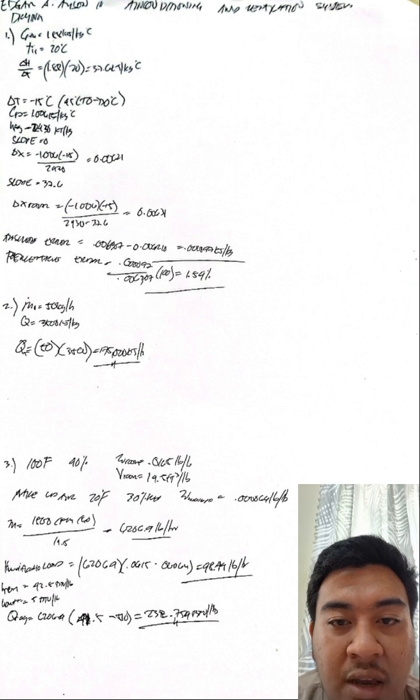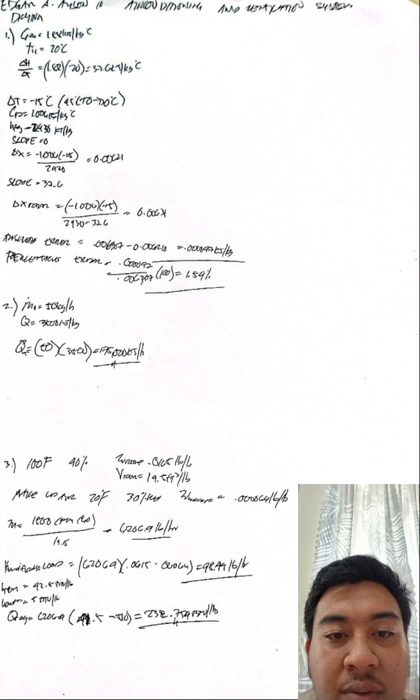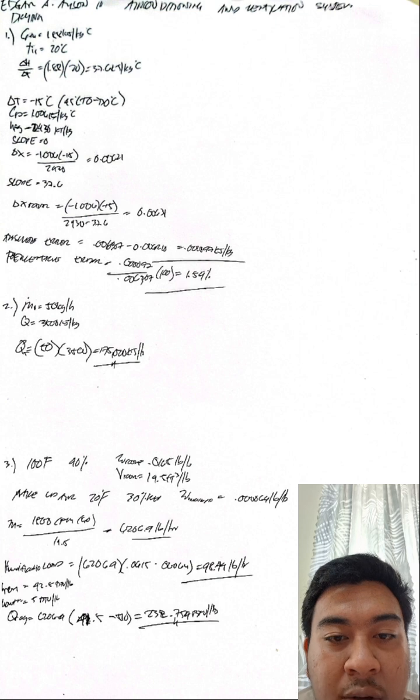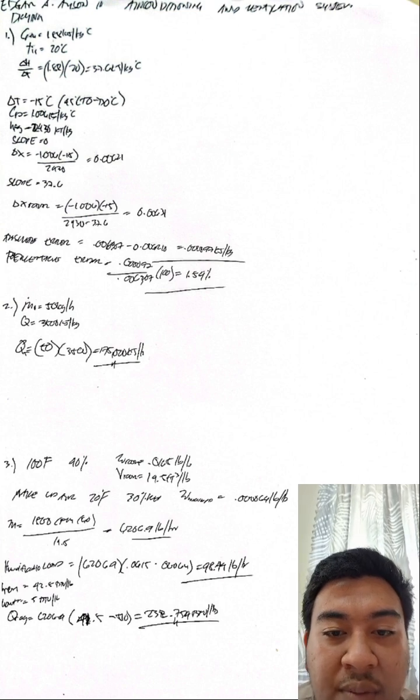The room has a humidity ratio of 0.0165, while the makeup air is only 0.00064. The difference times the mass flow gives us a humidification load of about 98.7 pounds per hour. For heating, room air is 42.5 BTU per pound and makeup air is 5 BTU per pound. Then multiply the difference by the mass flow, and we get the answer of 232,750 BTU per hour needed just for that fan.